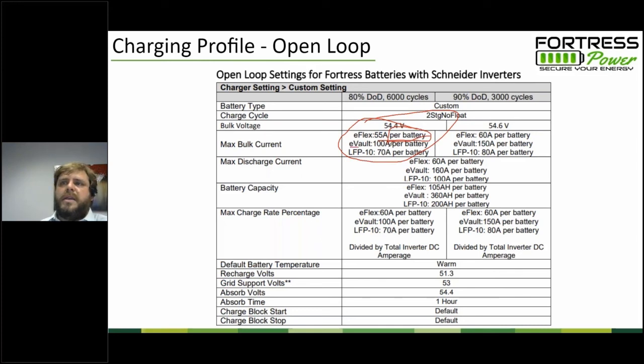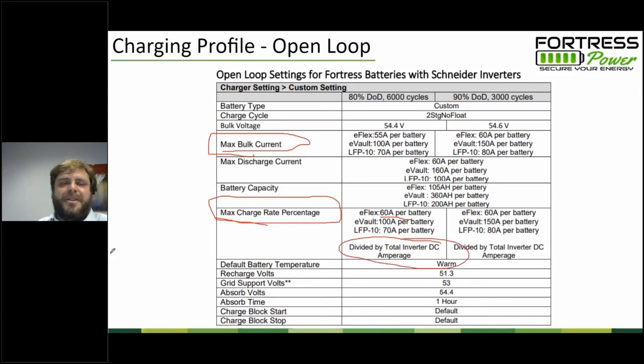And so if you have 1 eVault at 100 amps per battery as its max bulk current, then if you had 2 eVaults, the max bulk current would be 200 amps rather than 100 amps. Likewise with the eFlex, if you just put into your setting 100 amps and you have 2 batteries, the battery's going to charge a lot more slowly. This is a per battery current. Some inverter manufacturers, instead of a maximum charge current, have you enter a maximum charge rate percentage, where you basically do the same thing, but you divide by the total capability of the inverter supply to get not the charging amperage, but the charging amperage as a percentage of what the inverter could theoretically supply.